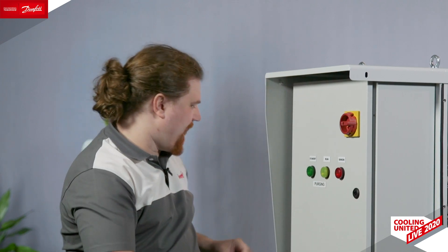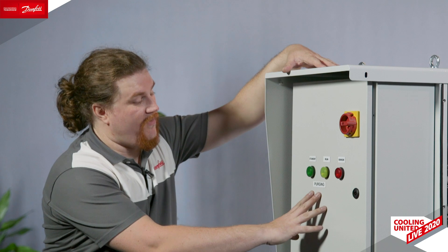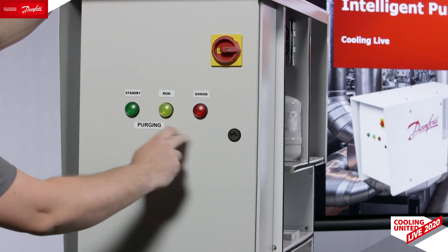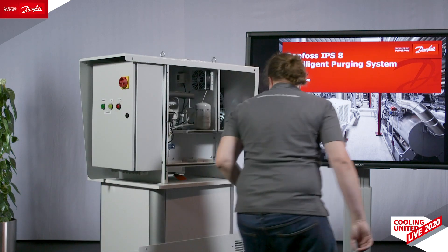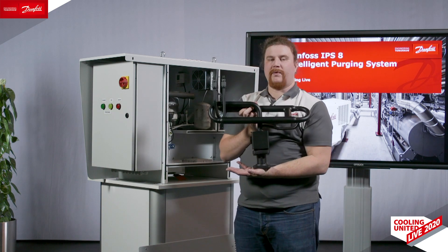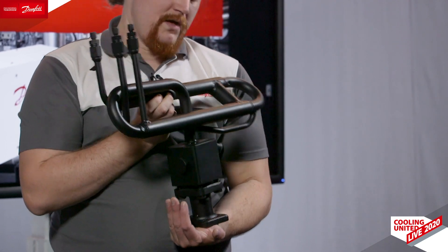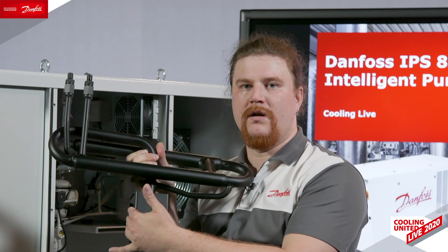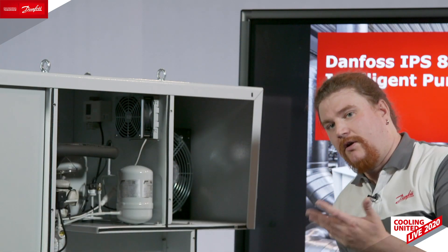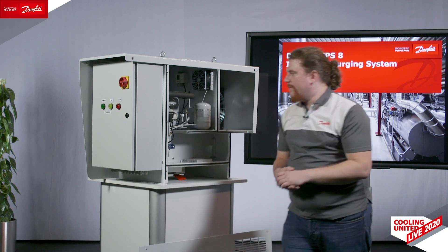We have a very nice indicator here so we can see from far away what the device is doing — for instance, whether we're in standby, waiting, compressor running, purging mode, or if there are issues. The last but very important part is the patented Danfoss evaporator for the IPS-8. Very simple design, but with interesting features. For example, there is a special port for one of our additional products recently released, called LLS — the liquid level switch. This small device can help us understand when there is liquid inside the IPS so we can stop the machine and wait until it drains.